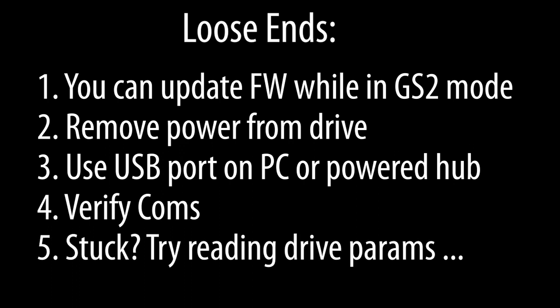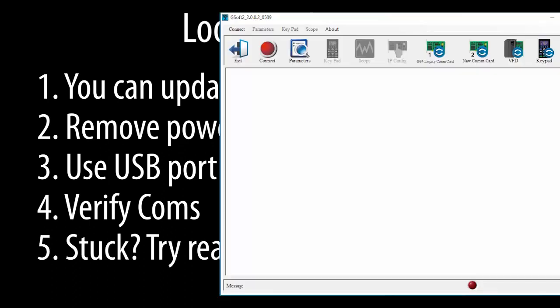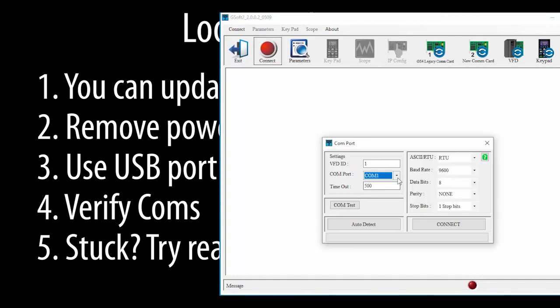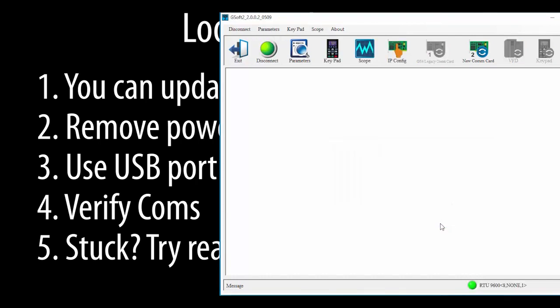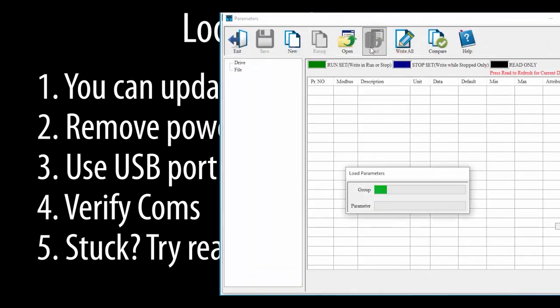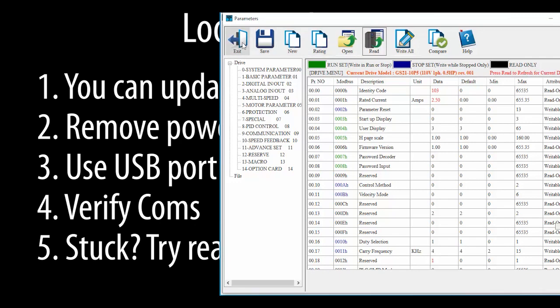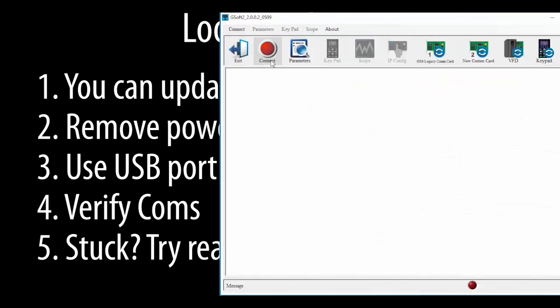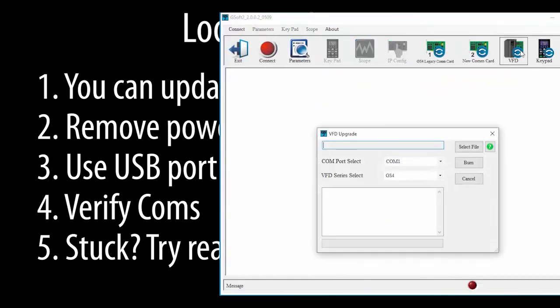If the firmware update process has trouble connecting to the drive or the comm port, then try this. Connect to the drive, read the parameters, disconnect from the drive, and then try the software update again. This is a neat trick if the drive gets stuck in some weird mode that prevents the firmware update from working.